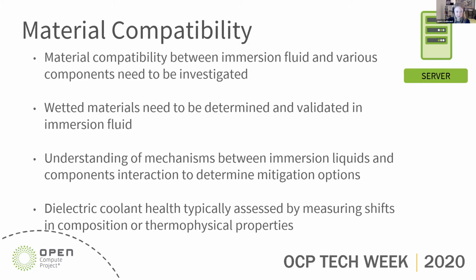It's not necessarily that material compatibility is something that we don't have to consider with other cooling technologies. It's just that complexity has slightly increased, right? If you're taking a full system and putting it into a liquid, you need to make sure that there is material compatibility between the immersion fluid that is being used and all the components that are on the board. Therefore, it's also very important that you know what wetted materials you're actually putting into that liquid. You also need to understand the mechanism between immersion liquids and component interaction to determine mitigation options.